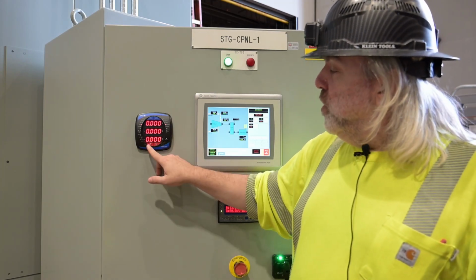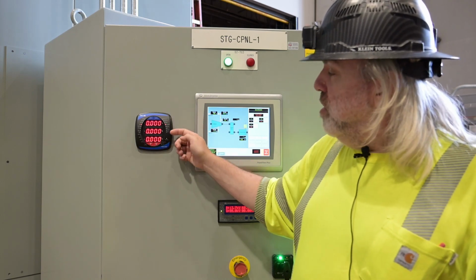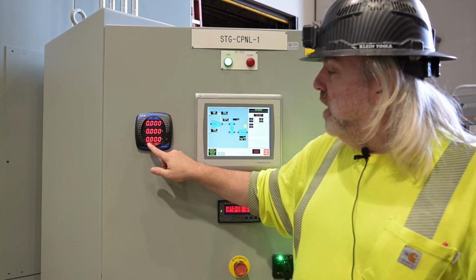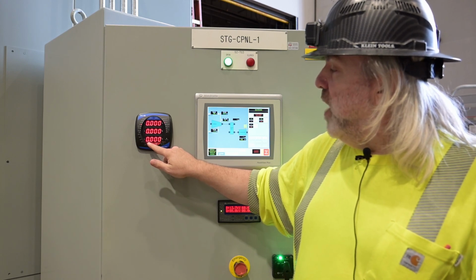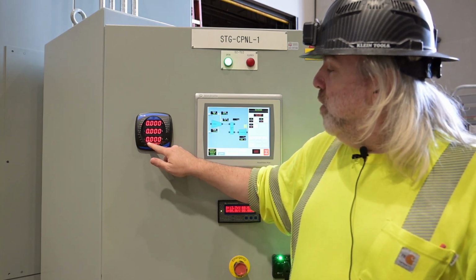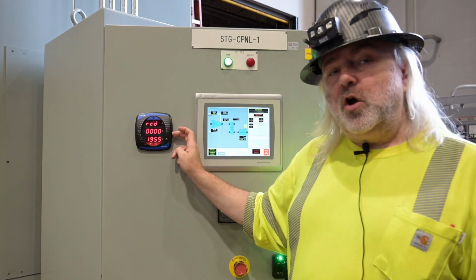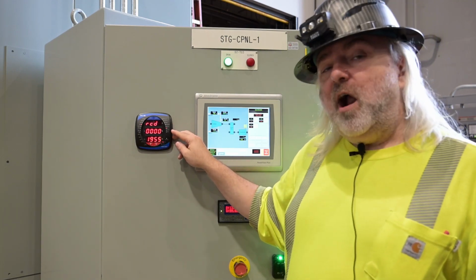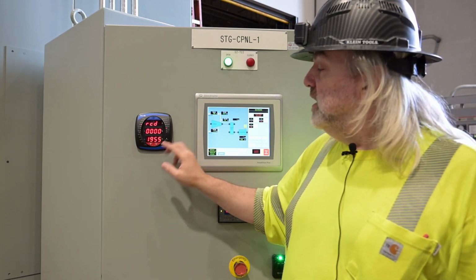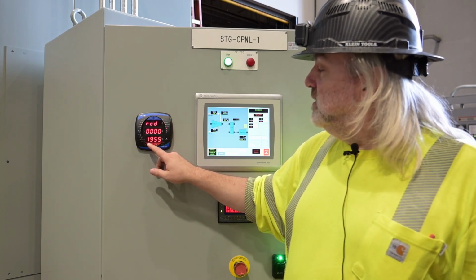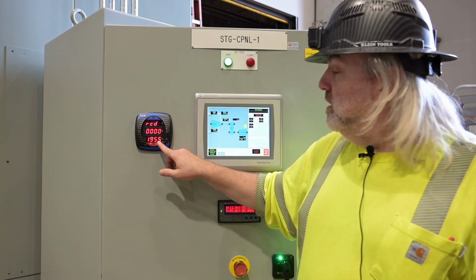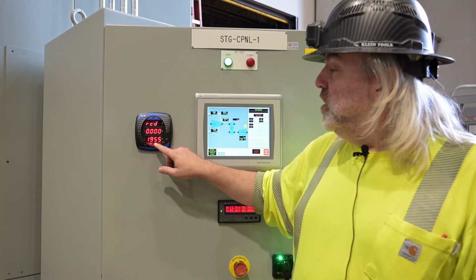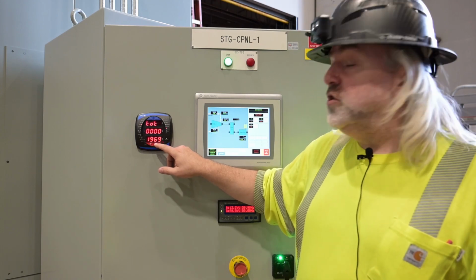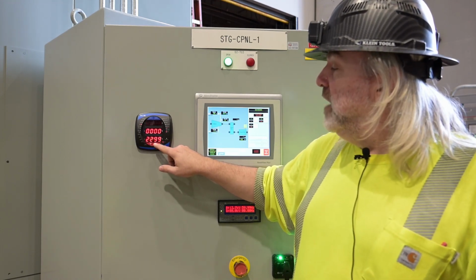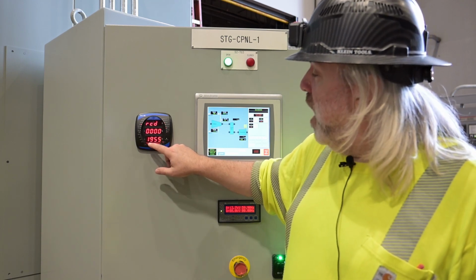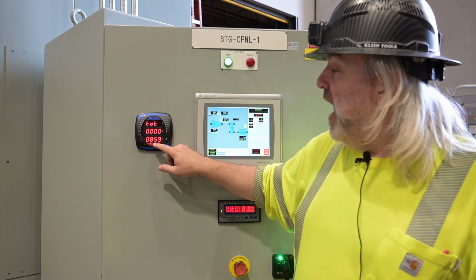To use the meter, we can use the down key to cycle through the available metering data on the side. As you can see, as I go down through, I have different indications. At the very bottom, we have our energy totalizer: a watt hour, a VAR hour, and a VA hour. Under all of these, once you achieve the desired metering section, you can use the side key to cycle through receive, total, receive, deliver, net, and total. You can do that for the watt hour and the VAR hour, not for the VA: positive, negative, net, total.